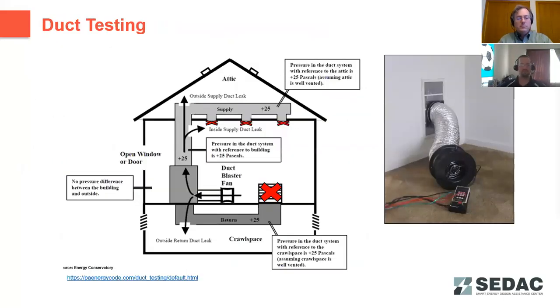So just an example of what that pressure testing looked like schematically. You're going to seal up all return and supply registers. You're going to pressurize that ductwork to 25 pascals. Usually that's done with a small connected fan that's tied into the ductwork. Pressurize that ductwork and get a pressure reading.